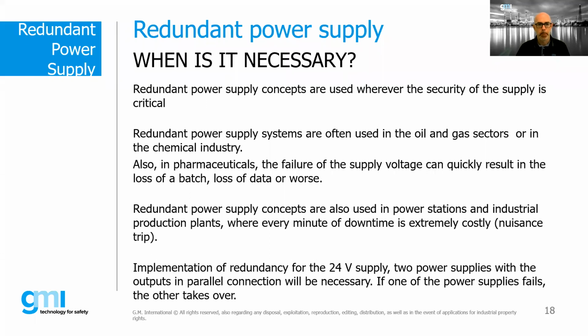Next slide, Andrea. A power supply redundancy system must be used when the safety of the power supply is essential. For this reason, redundant power supply systems are used in critical sectors such as oil and gas or pharmaceuticals, and in all those applications where the loss of power supply translates to the loss of sensitive information, or in all those applications where the certainty of having a correct power supply on request is fundamental. It must also be used in all systems where every minute of production downtime is extremely costly.